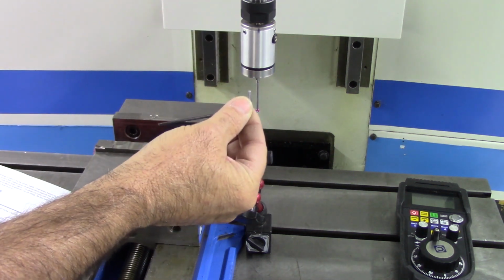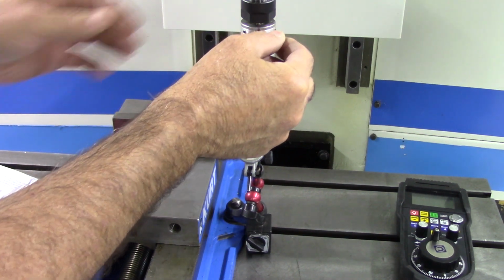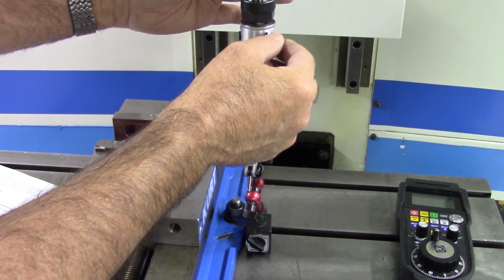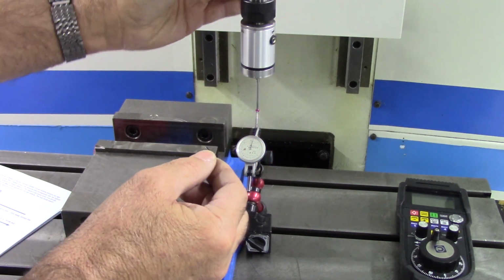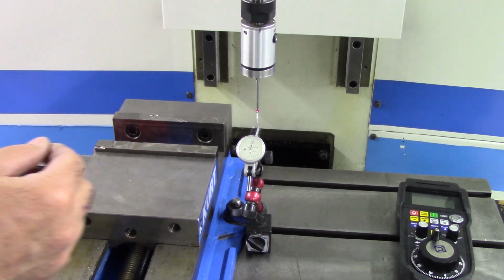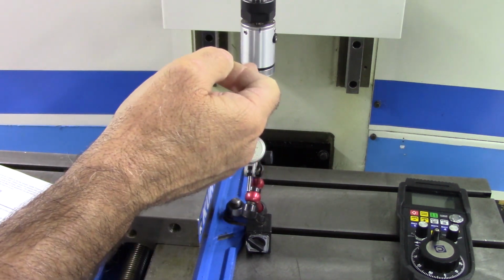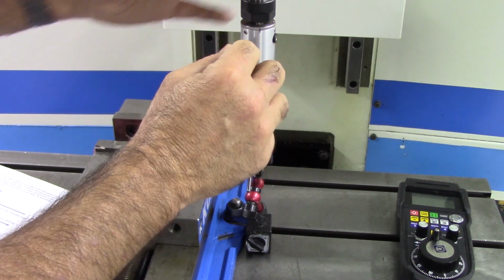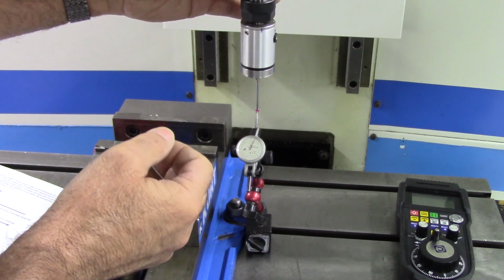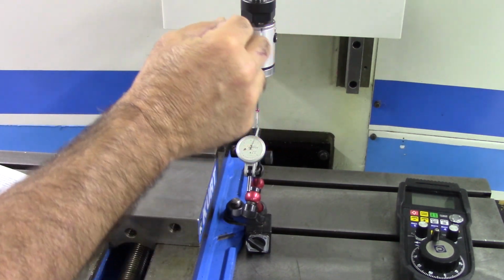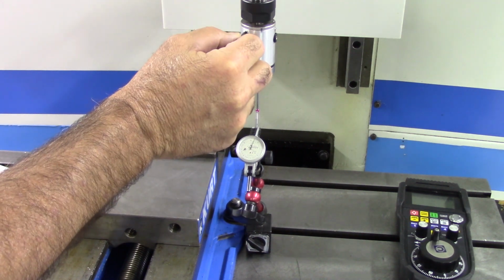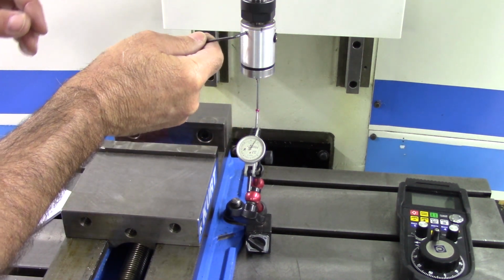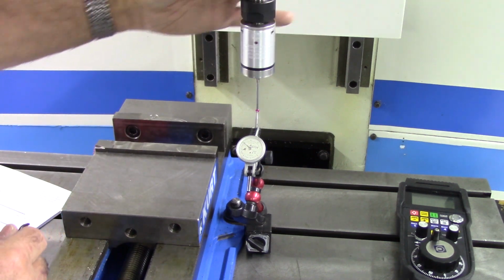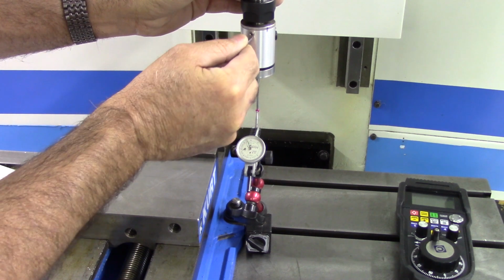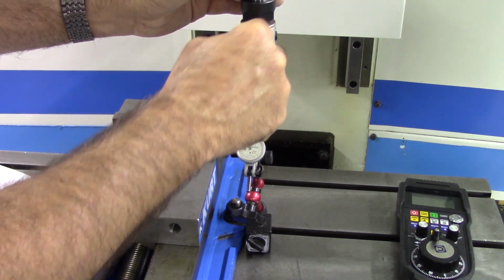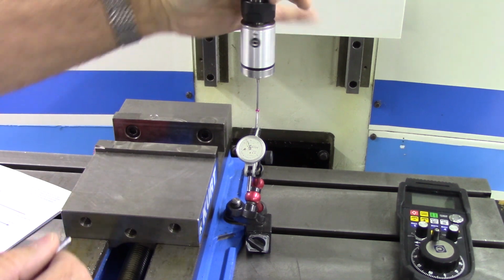And you're going to use the wrench, and you're going to tighten or loosen very gently, very tiny increments, these 3 set screws until you get it in. And turning the set screw clockwise moves the screw in, but the body will come out. So if you tighten the screw in, the probe tip's going to come out at you. So just take your time, take small increments all the way around until you get it dialed in. I'm going to go ahead and see if I can adjust mine a little bit. Okay, there we go.